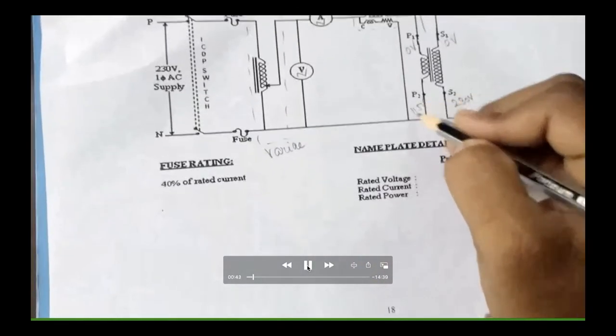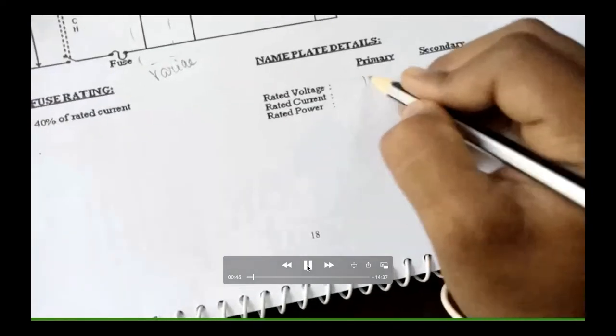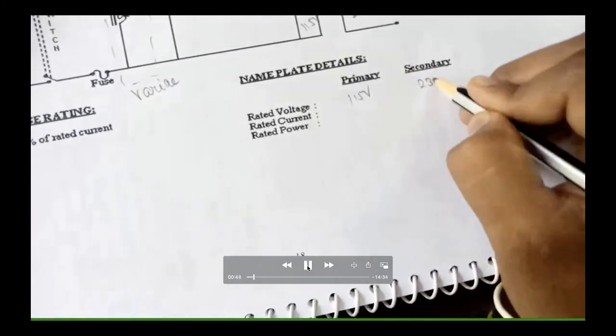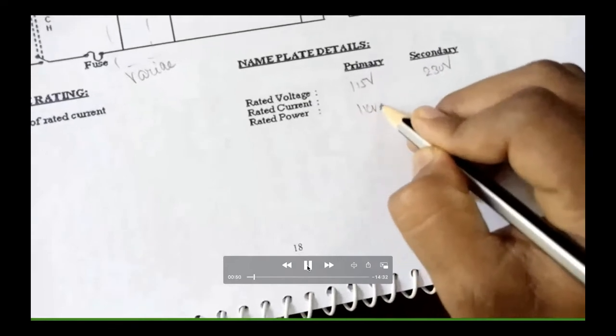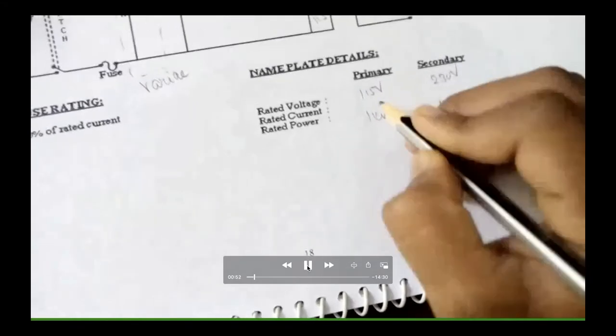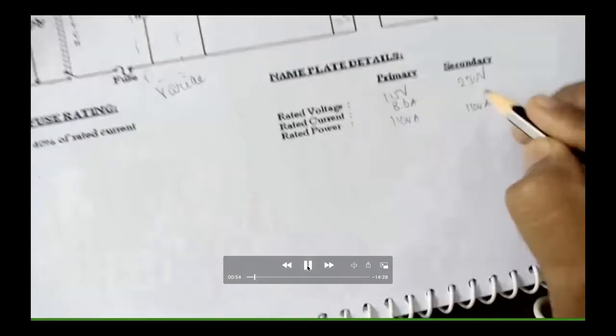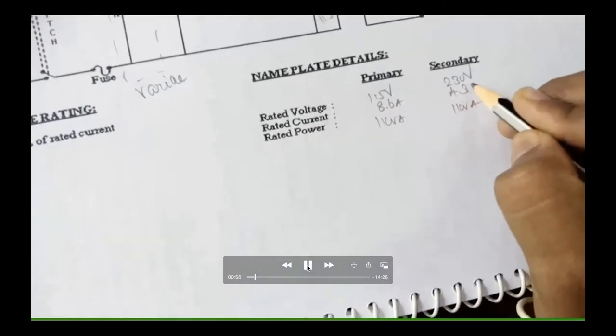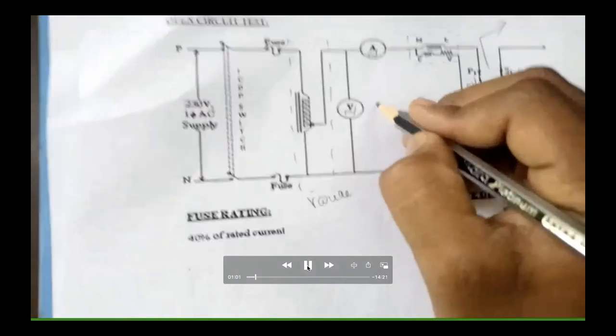Since the primary voltage is 115 volt, we can put 115 volt, and the secondary voltage is 230 volt, and it's a 1 kVA transformer. For a 1 kVA transformer, you can find out the rated current of the primary side and secondary side. The primary side will be 8.6, and the secondary side will be 4.3 amps. That is 1000 divided by the respective voltages.